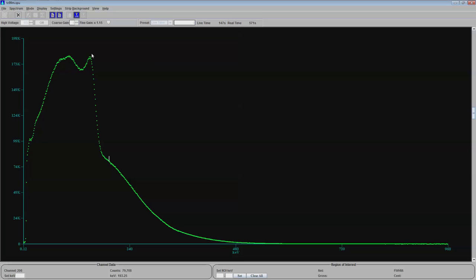So this is off a little bit. See, this peak right here registers as 150 keV in my machine. The reality is it should be 140 keV, the peak for technetium-99m. And that's all right. It's only off by 10 keV, which isn't bad considering what I had to do to get the calibration to come out to begin with.